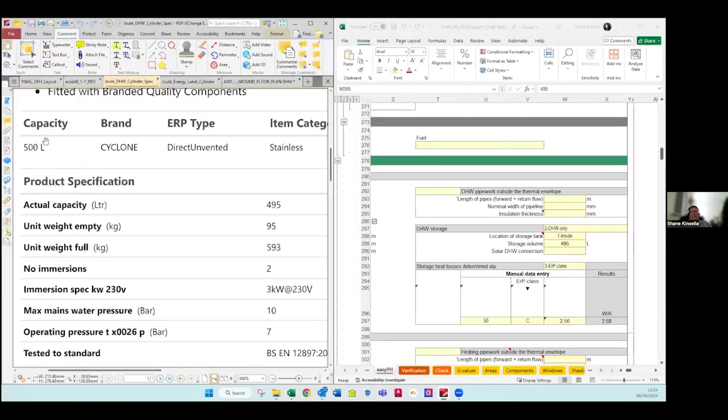But I've seen a case lately where we had a 200 litre cylinder sent into us, and when I actually looked at the real volume of it, it was actually only 178 litres. So that was quite a difference in volume, which was like 12% or something like that, in that order. So you need to always be careful that you're putting the actual volume in there.